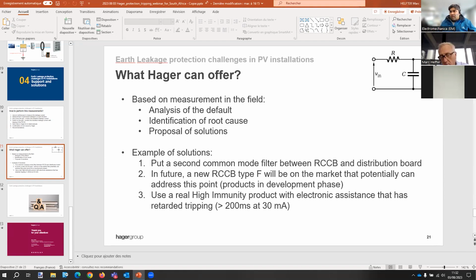What I'm trying to say is I've had it like 3 or 4 times where the client complained about the tripping of the earth leakage. And 2 times I noticed that the inverter was not earthed. The casing of the inverter was not earthed, neither was the battery. So sometimes I use the 2.5 mil cable. It solves the problem. Sometimes it doesn't work. So I was wondering, maybe the earth cable needs to be bigger? Maybe use a 4 mil or 6 mil cable, because the tripping of the earth leakage is sensing any current leaving the circuit. So I don't know if I'm making sense.